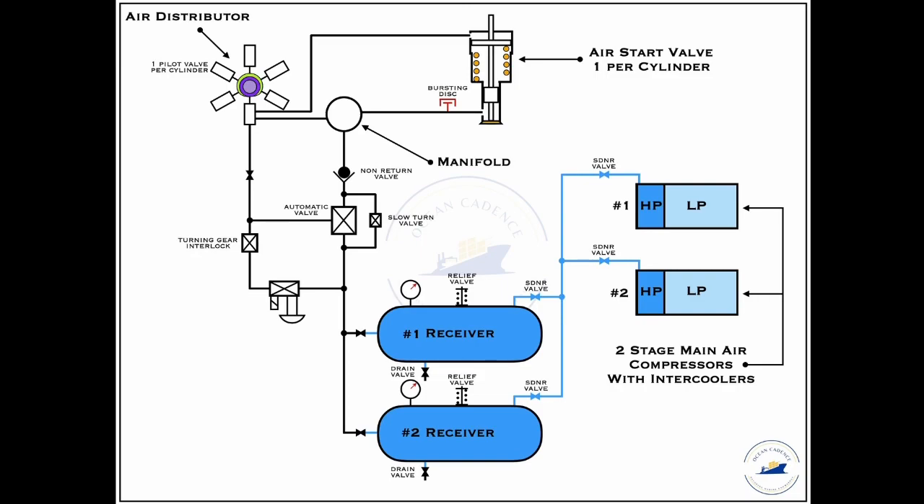This 30 bar air then proceeds further into the network and either with the help of a remote start signal or a local start signal can be admitted further into the line. From here, before the air proceeds further, it has to be made sure that the turning gear interlock has been actively removed — meaning the turning gear is no longer in place — so as to ensure that the engine is ready to be started on air and then further on fuel.